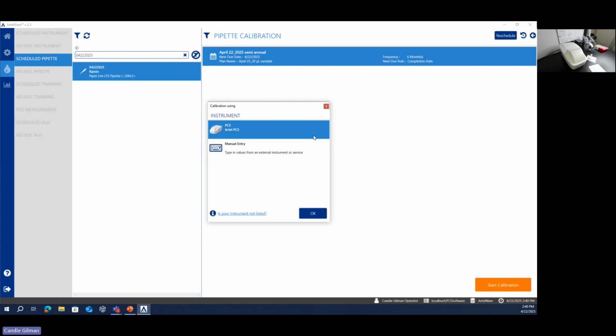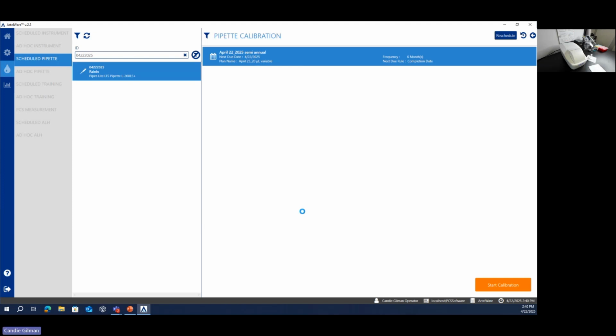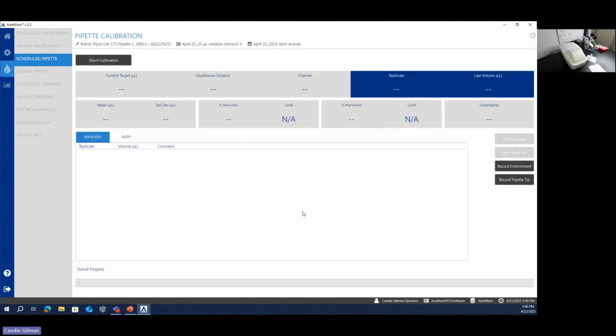Now, I have a couple of options. I can calibrate with the PCS, or I can manually enter in some data. Well, of course, today is a PCS demo. So I'm going to go ahead and select the PCS and click OK. And then from there, I'm following the software prompts. So at this point, I'm being asked to scan the Qual-Assure 3 bottle. So I just want to show you real quick, this solution specifically can run 10 to 49 microliters. So I'm going to go ahead and scan this bottle as per the software instruction.